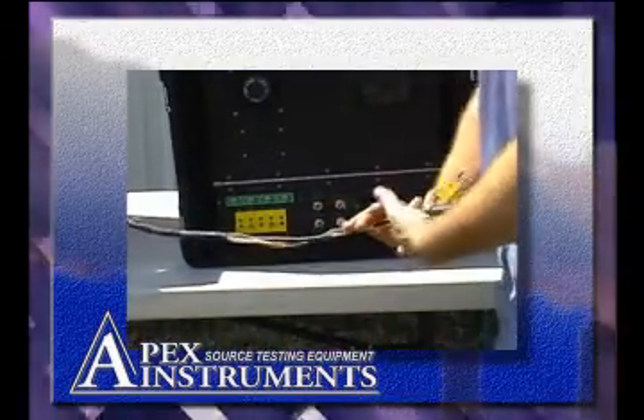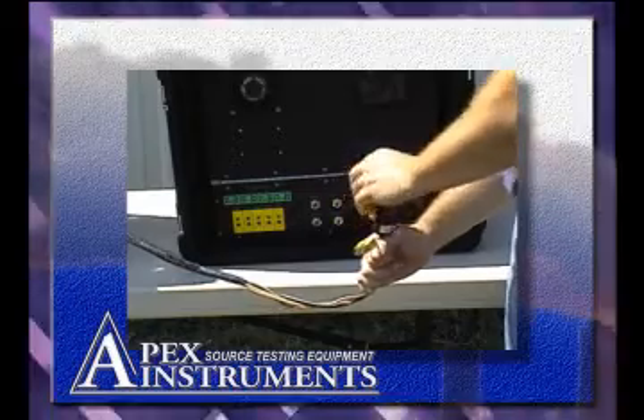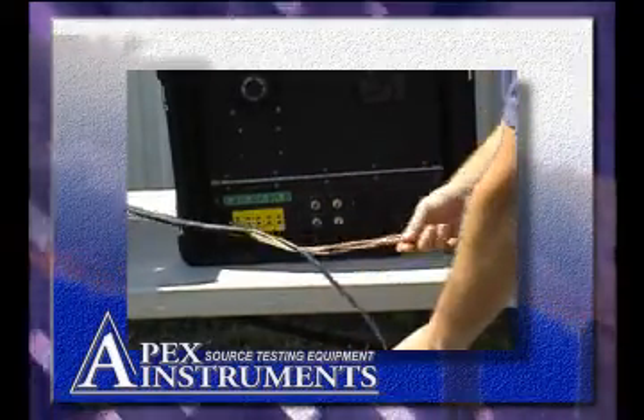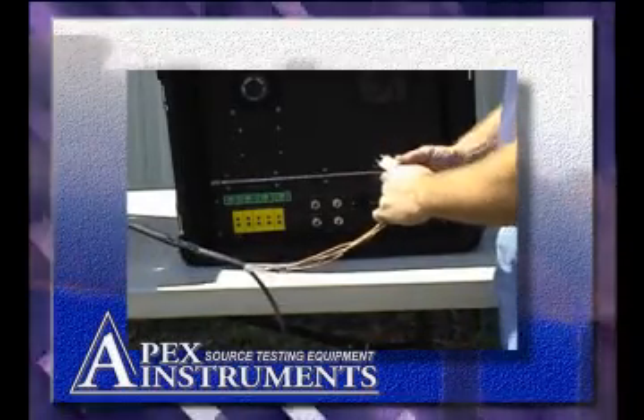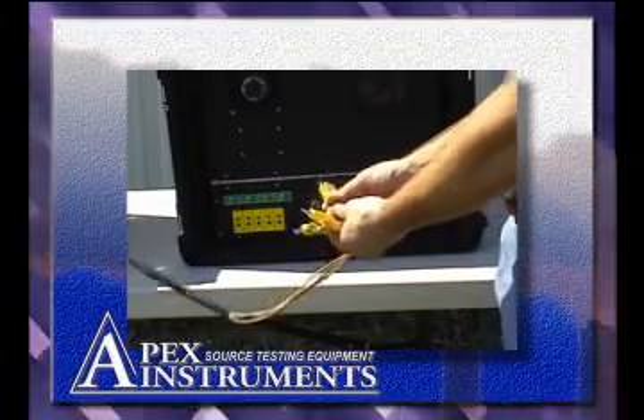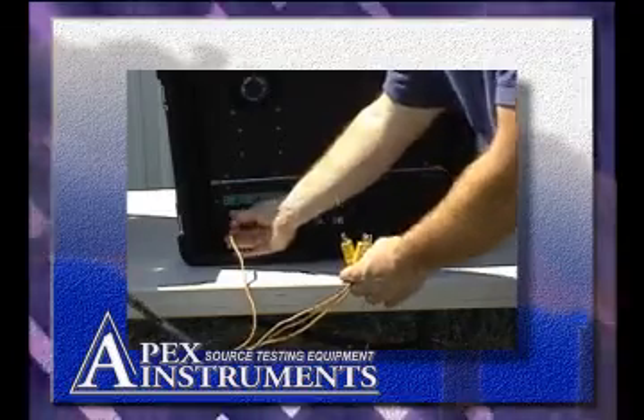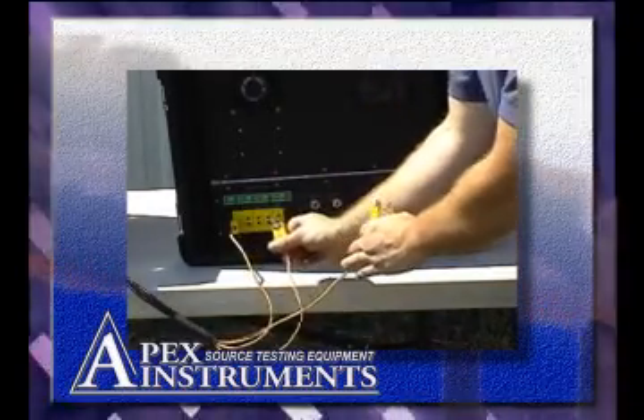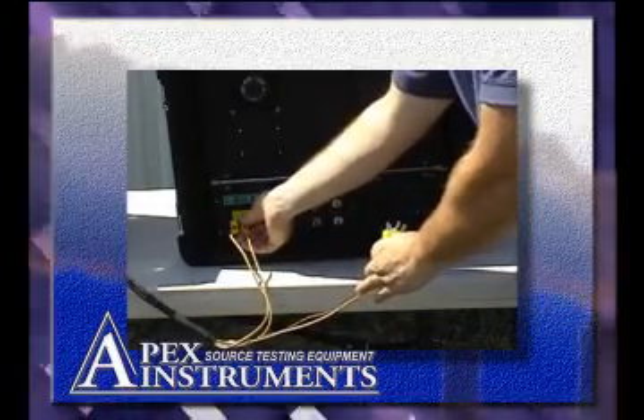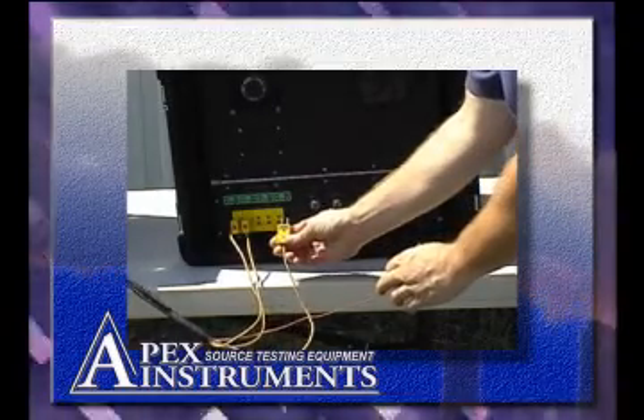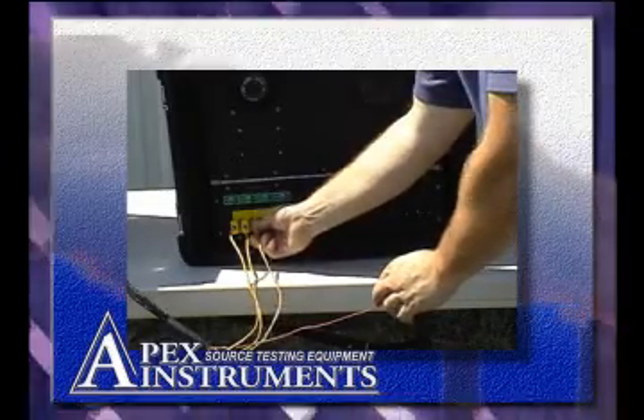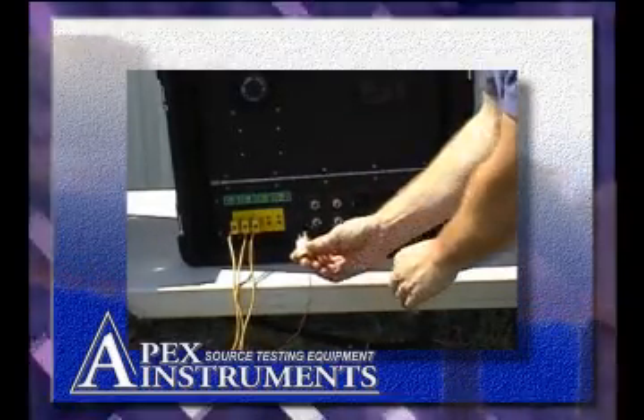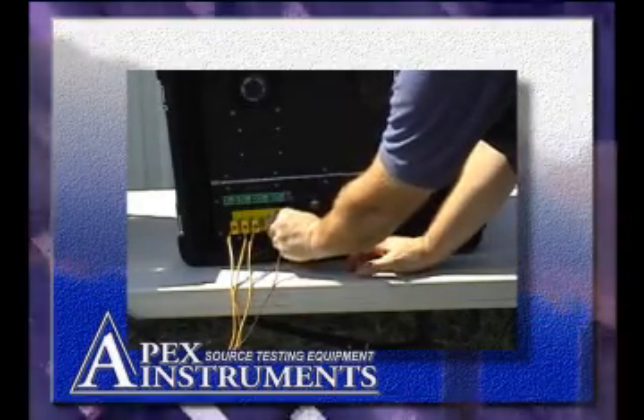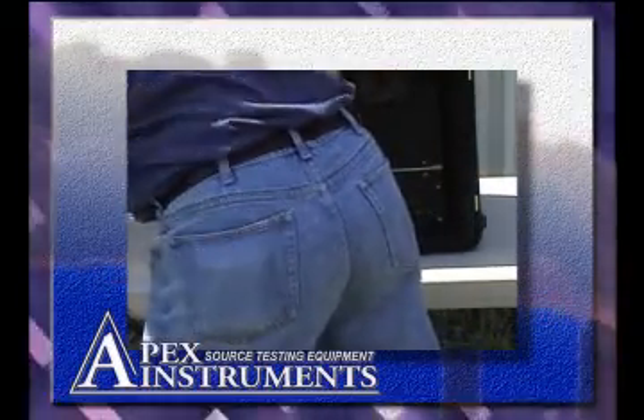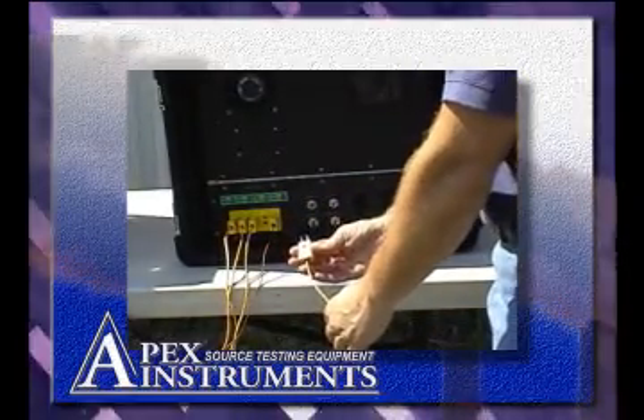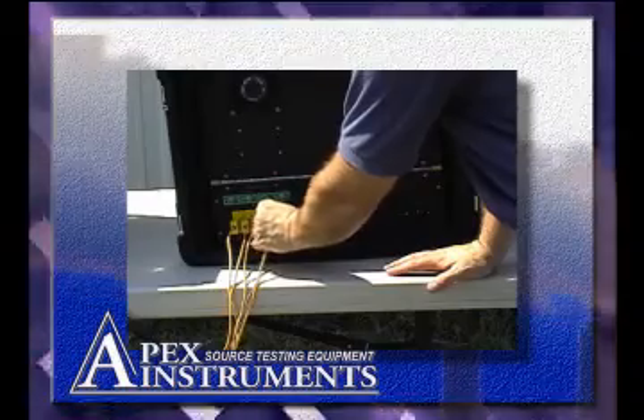The operator should connect the thermocouple connections from the umbilical and the chiller to the XC-6000 console. Stack to stack. Trap to trap. Probe to probe. Heated self-regulated line to the auxiliary input. The final thermocouple connection is the chiller to chiller, following the labels on the connectors.